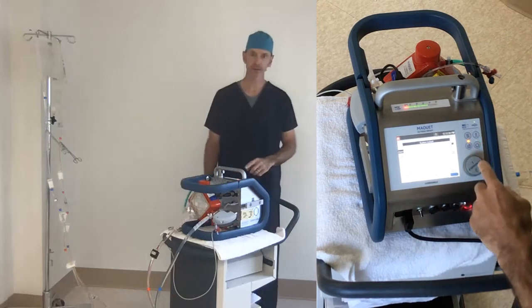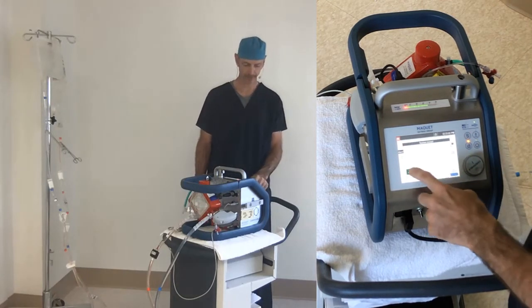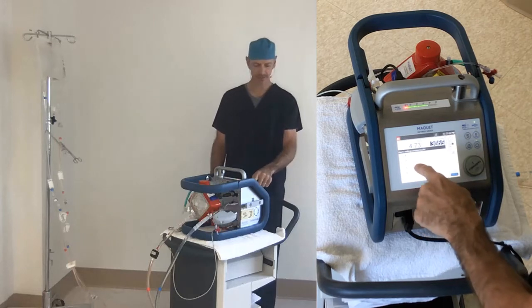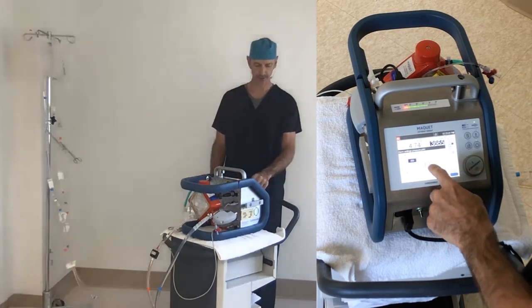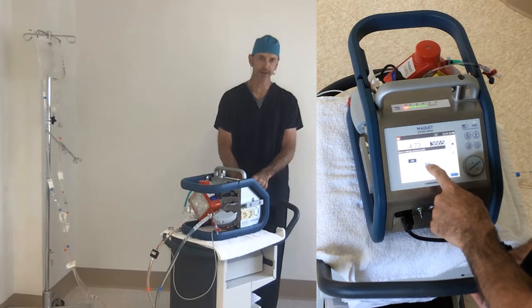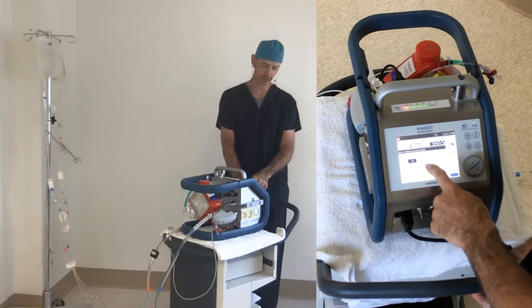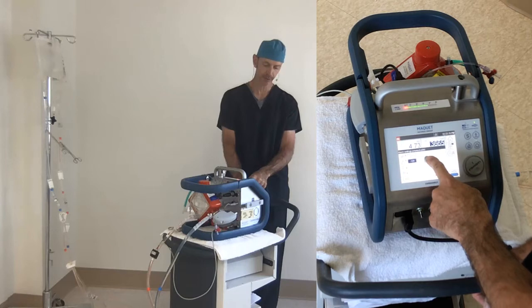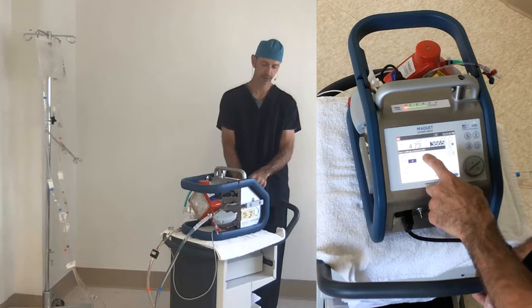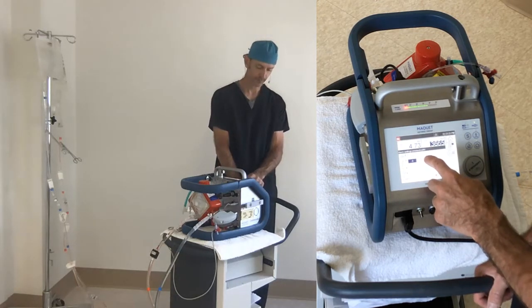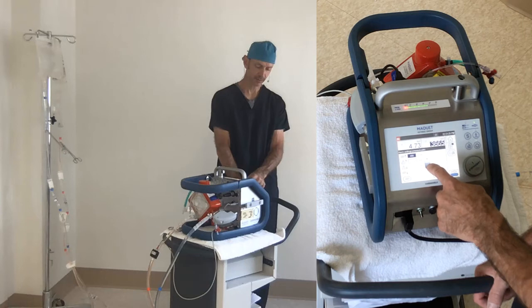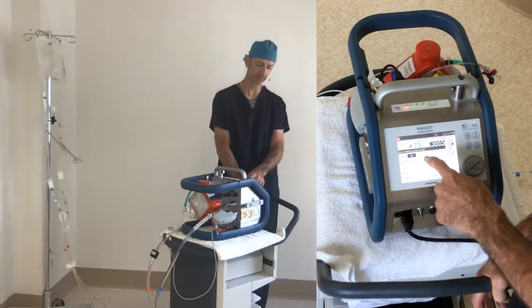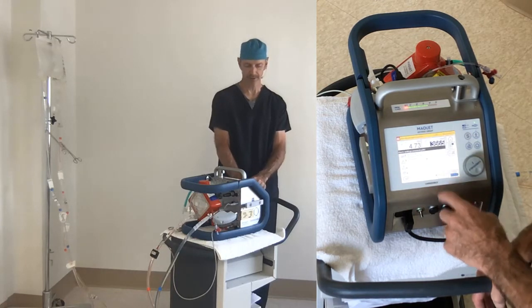So let's demonstrate how pressures can stop the pump. Right now the limits are set to 400 and 500. I'm going to turn that 400 down. I don't want any audible alarms right now; I just want it to go straight to stopping. So I'm going to set this to close to 0. And then let's set this 500 down to something we can easily reach, say 350. 327 sounds good. I'm going to enter that.